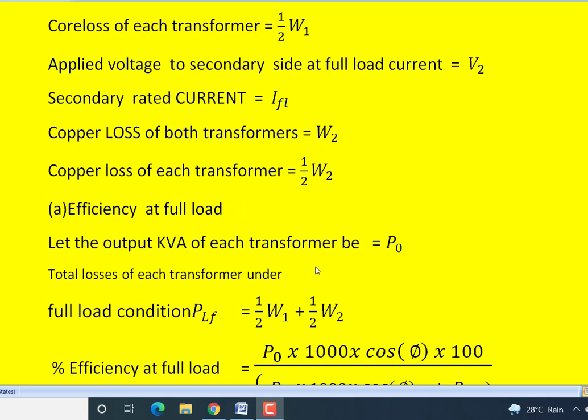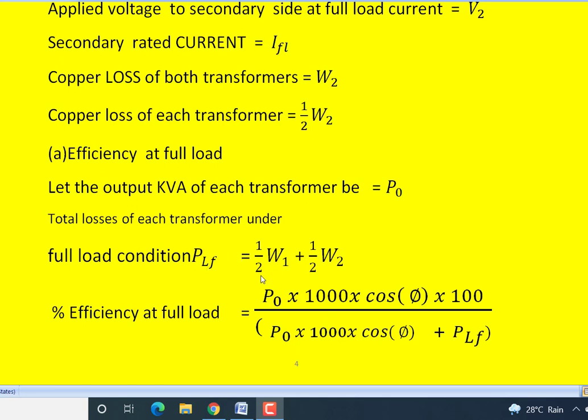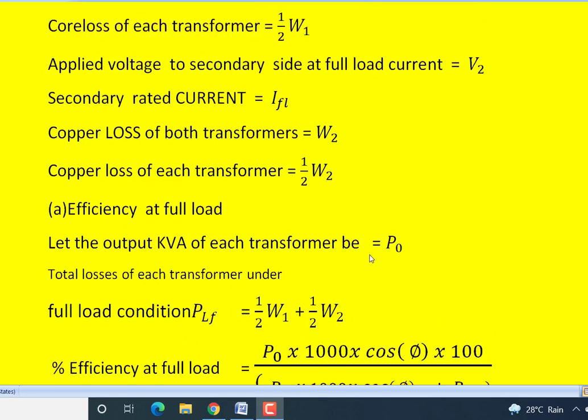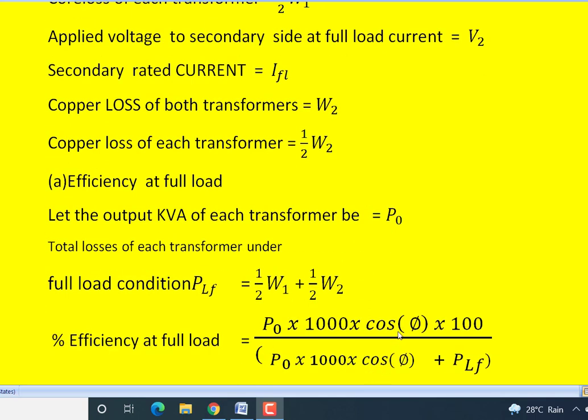So let the output kVA of each transformer be P0. Then the total losses of each transformer under full load conditions we represent as P suffix LF, which is equal to the core loss of each transformer, W1 by 2, plus the copper loss of each transformer at full load, W2 by 2. So we know the total loss and the output power, and we are calculating this efficiency at a power factor cos phi. So the output is nothing but V I cos phi.